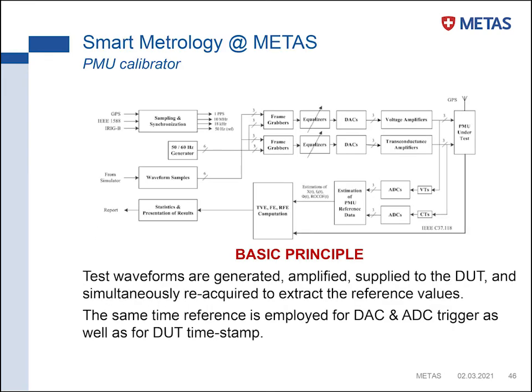Now, this is the standard. This is what measurements want to do. And how do we check this in METAS? So in METAS, we have a PMU calibrator that is more or less organized as in this scheme. I won't enter into the technical details, but what we do is generate the test waveforms as defined in the standards, and we amplify them in terms of voltage and current up to the levels expected in the field. We supply them to the PMU under test, then we downscale them by means of voltage transducer and current transducer, and we reacquire them.